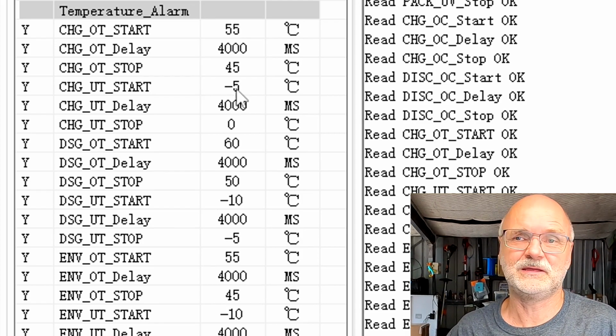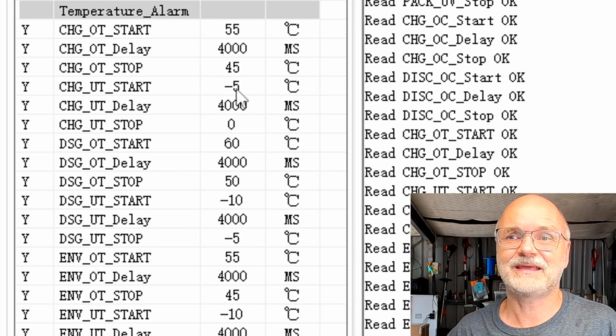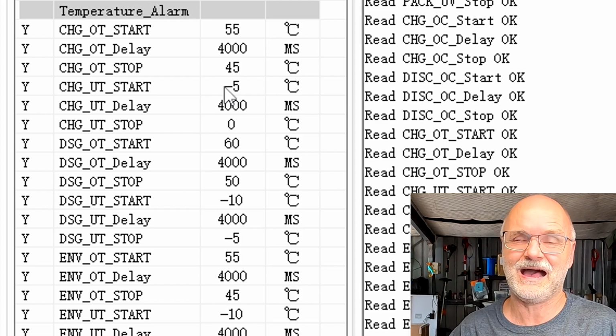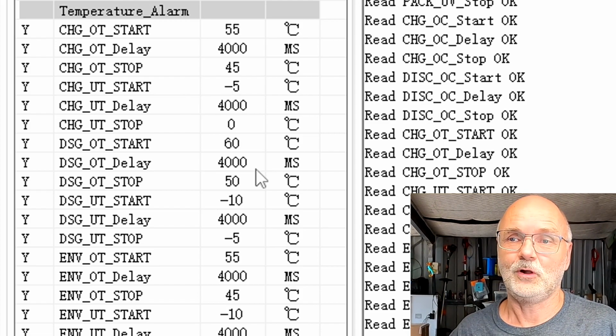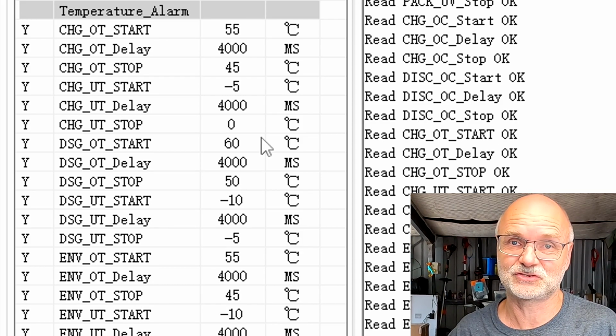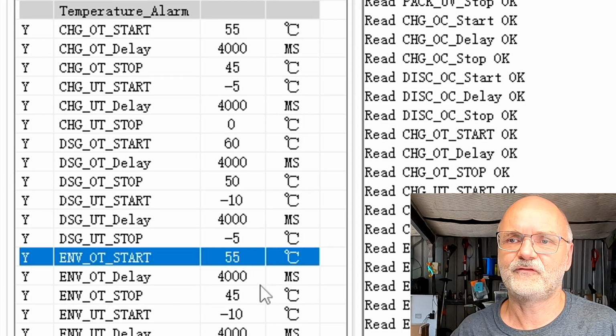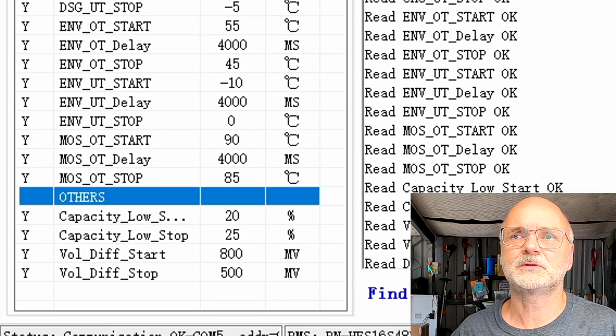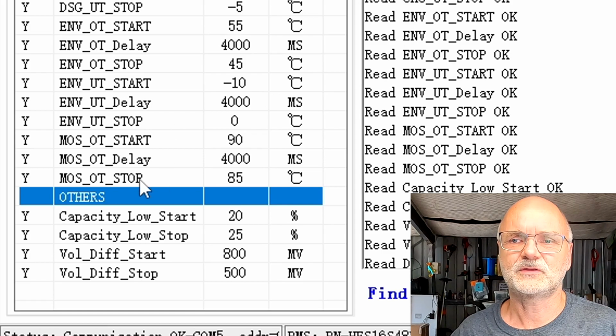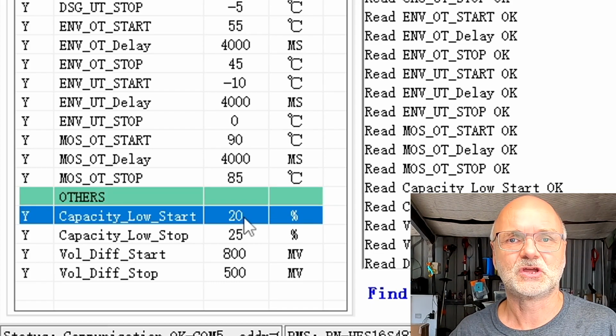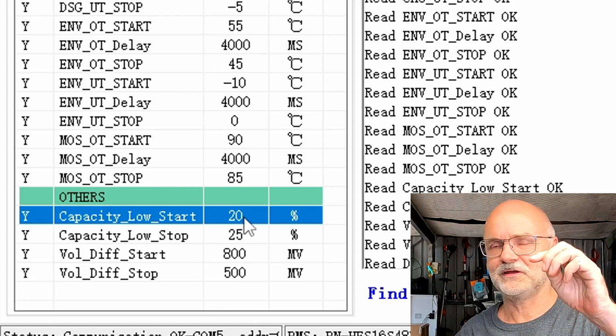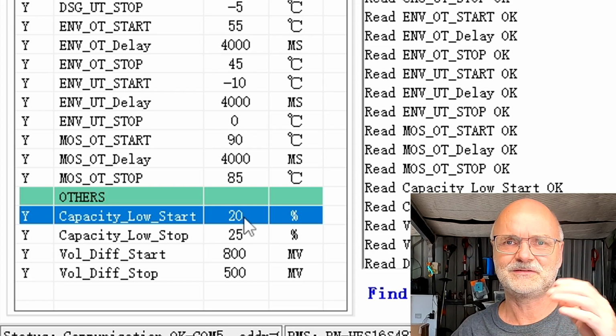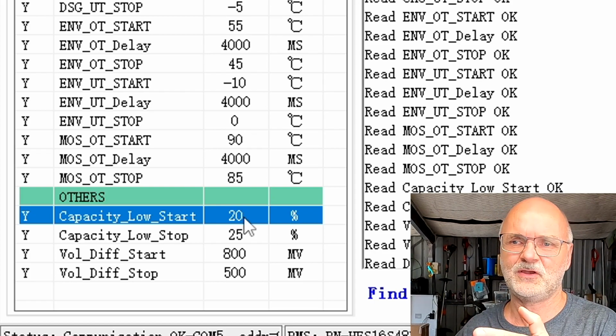The under temperature should be at about 10 degrees, I guess, but -5 is already in the damaging part where you shouldn't charge your battery at all anymore. So all these temperature settings need to be revisited and changed. We've got the environmental at 55. And on here we've got an interesting, let me just make this column a bit wider, a capacity low warning alarm at 20% state of charge. So I think this is a good parameter, but well, it doesn't work. As we did the first initial discharge capacity test of the battery, which didn't work, I was down to 12% and there was never an alarm coming up, neither in the software nor in the Victron system, nothing.